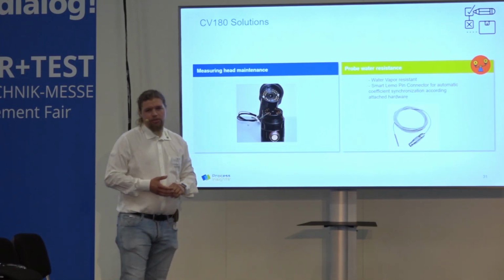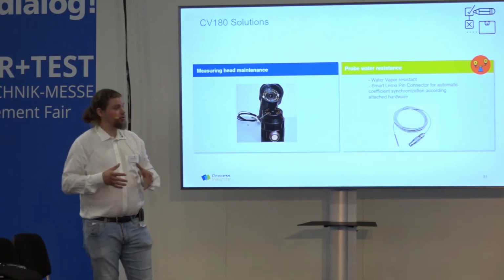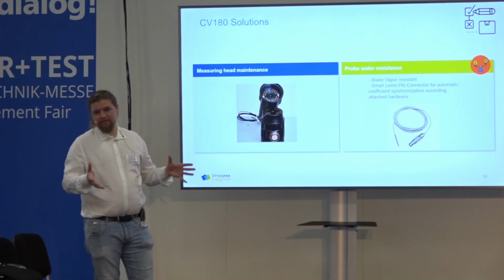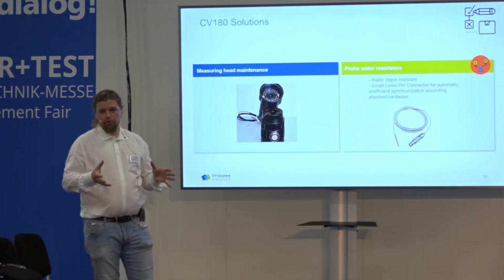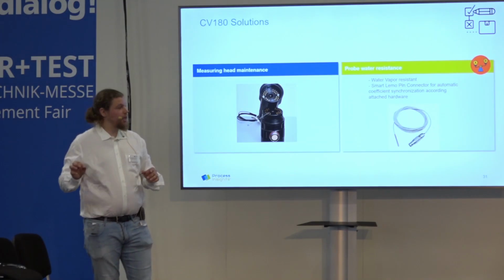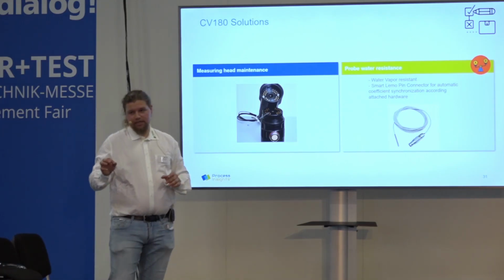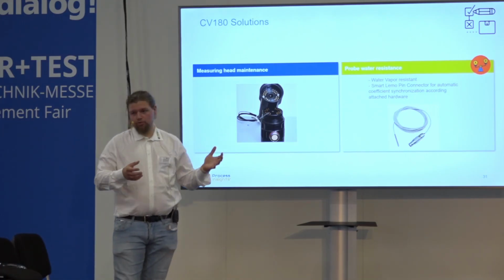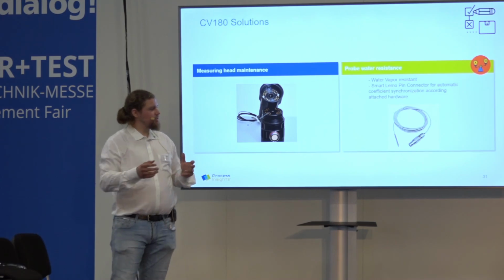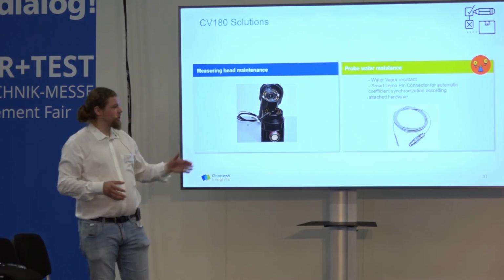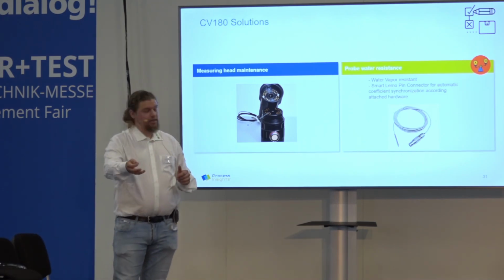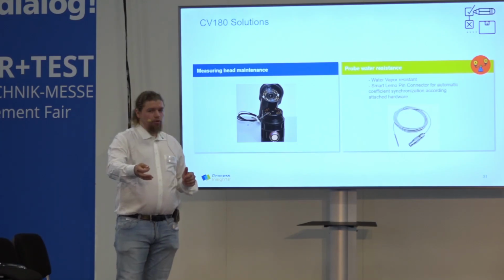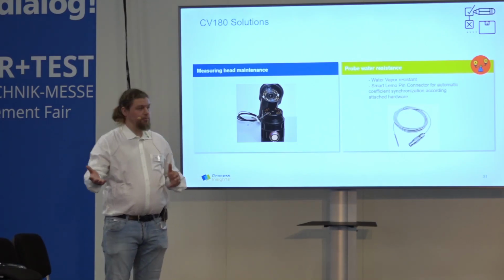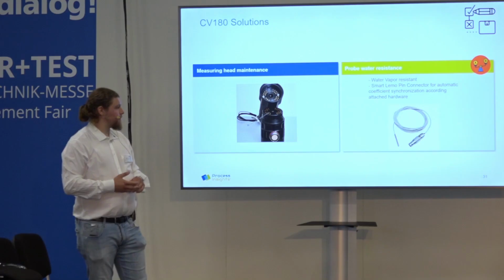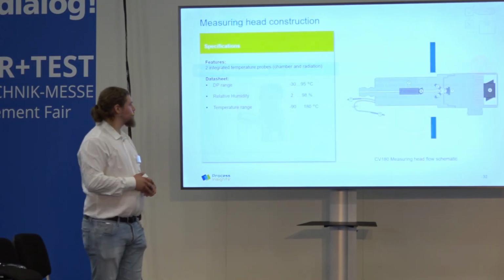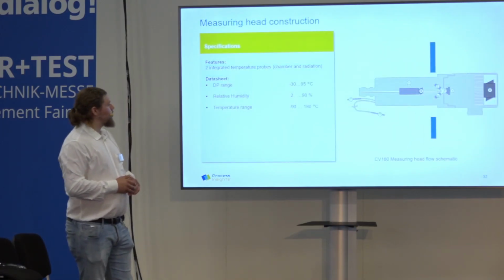There is a built-in smart chip which allows to store the coefficients. So in case you have 10 or 12 temperature probes and you need to get all the values in the unit, then maybe one temperature probe fails or is missing, then you would need to type in new coefficients. This solution allows to plug the probe in, and the coefficients will be read automatically.